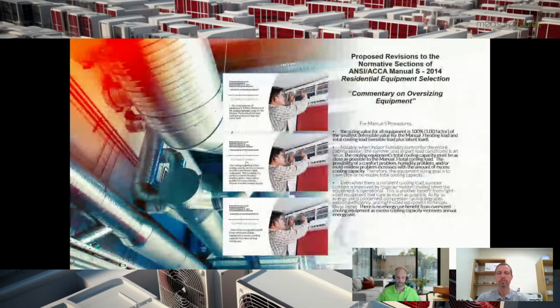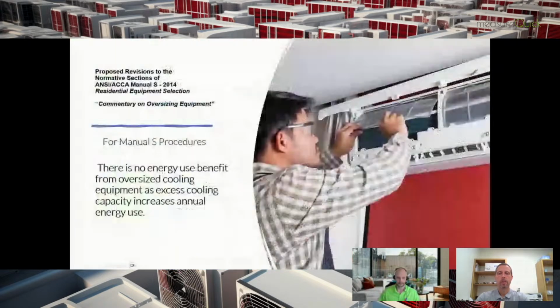And the last is a statement here. It talks about there is no energy use benefit from oversizing cooling equipment, because the excess cooling capacity just increases the annual energy usage because it's unnecessary, and people can be comfortable if the equipment is sized correctly instead of oversized.